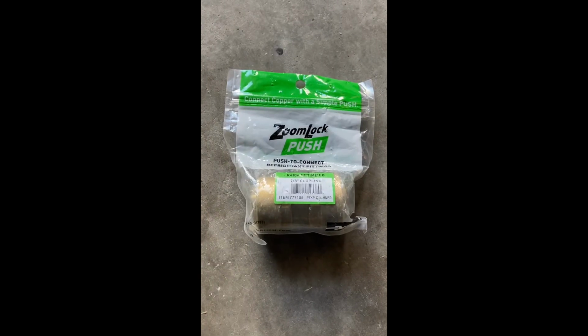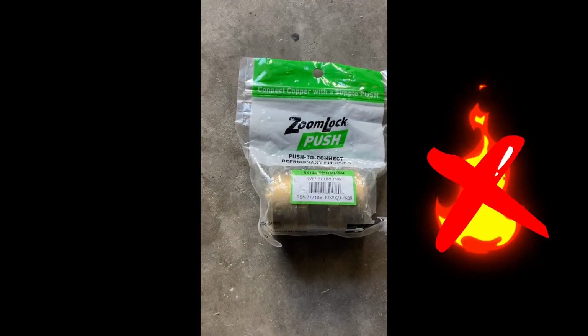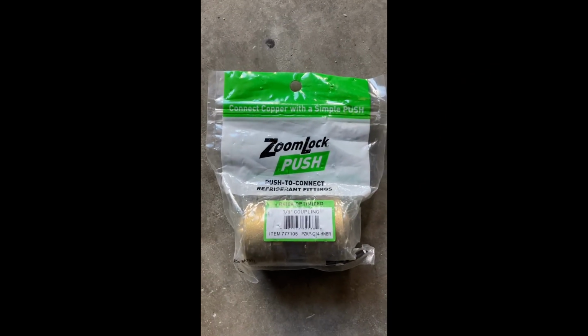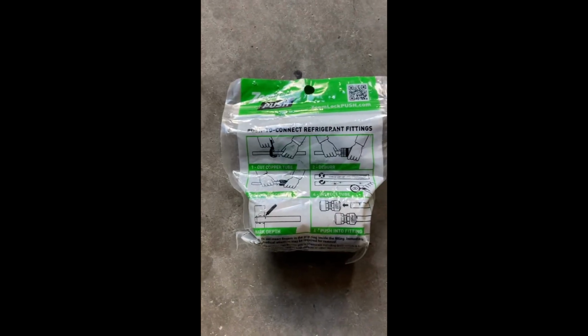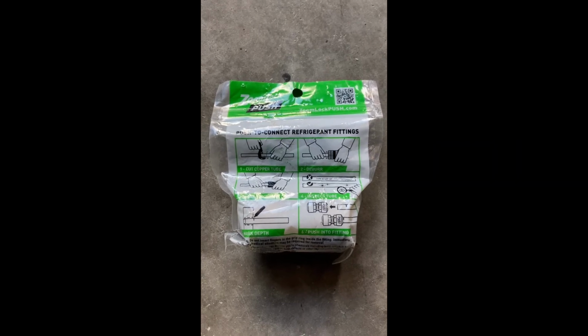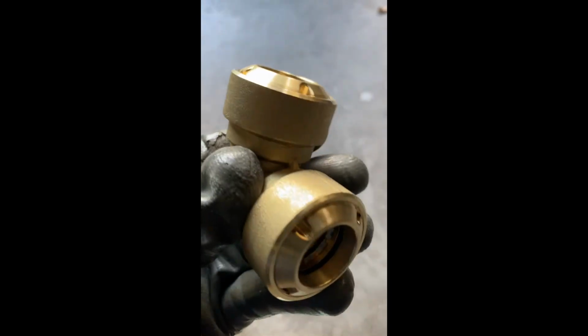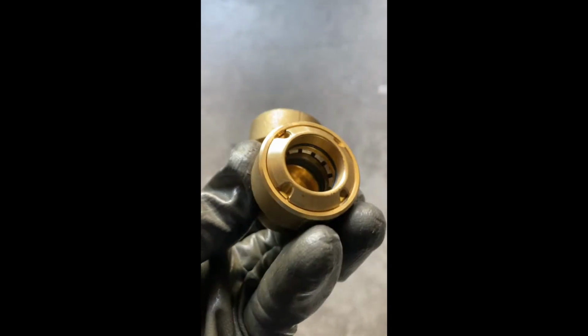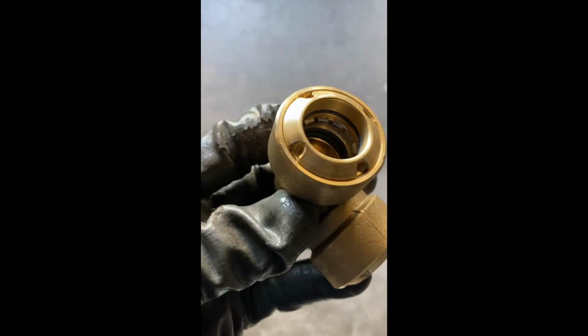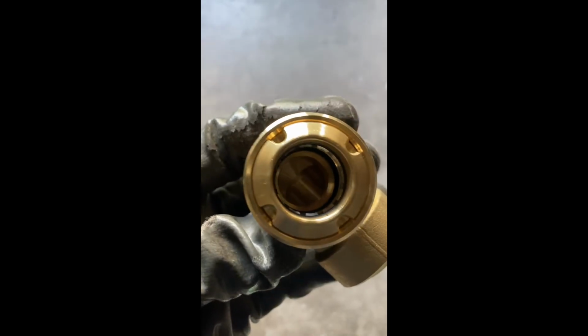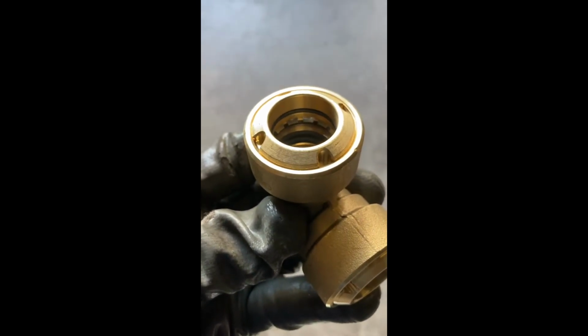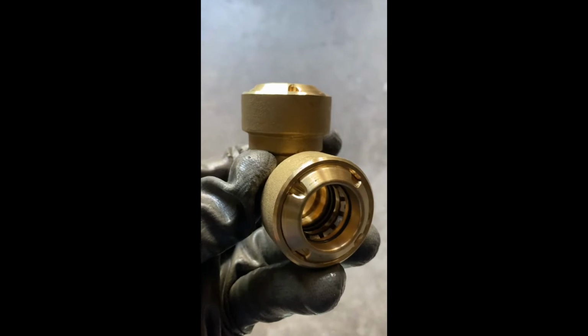So if you're working in a facility that doesn't allow hot work, meaning no torches, you can use these Zoom lock push fittings. They come in different sizes. These are R410A compatible, and they're simple and easy to use. They're similar to the SharkBite fittings you find like in plumbing applications. You have multiple O-ring seals inside. Do not stick your fingers in there. Keep them packaged up until you're ready to use them.